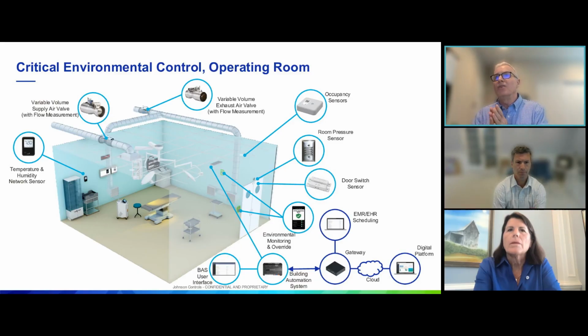So if we start in the upper left there and we look at that sensor, it shows 72 degrees on it. That's temperature and humidity. So, that calls out certain thresholds within 170 that we'd have to maintain. And the reason for that isn't, like, typically you think of those conditions as something for comfort, but it kind of goes beyond that for an OR, because if we're outside those thresholds, we could have microbial growth. We could have bacteria, mold, things like that, because we're outside of that humidity and/or that temperature.